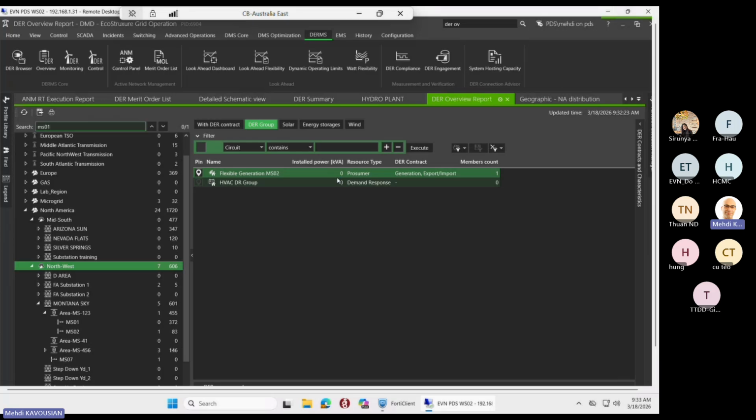So what is the concept of a DER group? We don't communicate with individual DERs. There is some controller or aggregator that actually controls them. We just talk to that master, saying, okay, you need to curtail this much. Inside that, it might have a solar unit, and it might decide to send the command to the solar, or it might have a battery and send the command there.